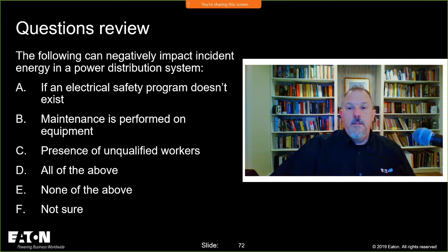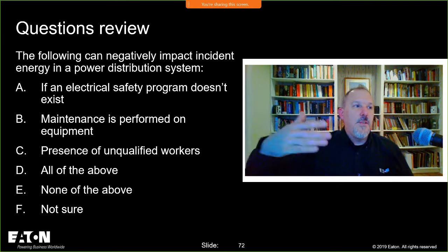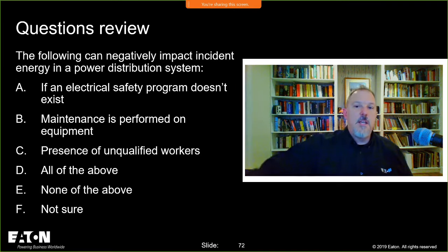Yes. Phase to phase also means leg to leg. In single phase, yeah, that's phase to neutral, really. In a single phase, it's a phase to neutral. It's not phase to phase because in a single phase, I've got that grounded conductor in that picture. It's really the phase to neutral.